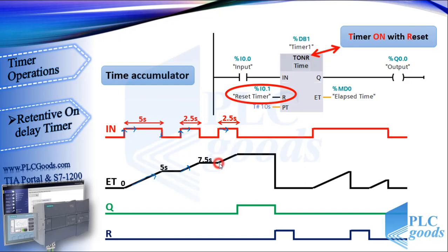When the third pulse appears and the ET values reach the preset time, the timer activates the Q output. The Q parameter remains set to 1 even when the signal state at the IN parameter changes from 1 to 0.